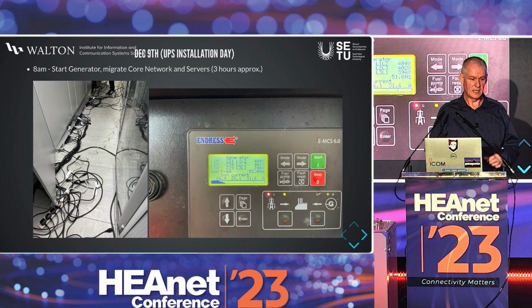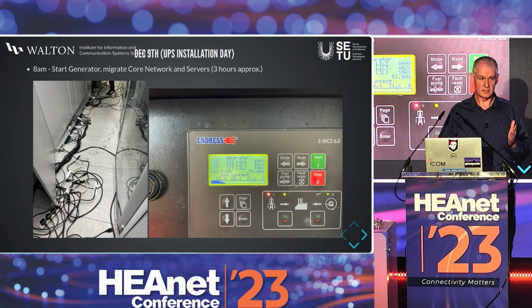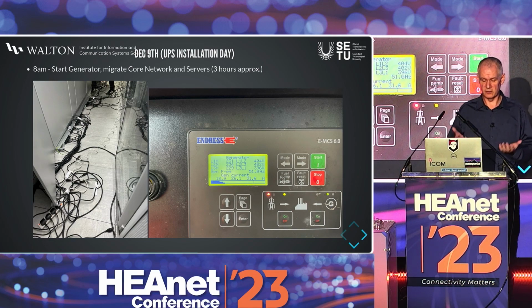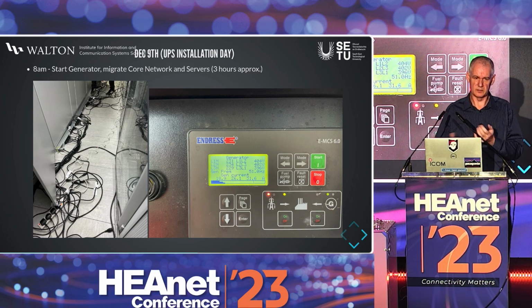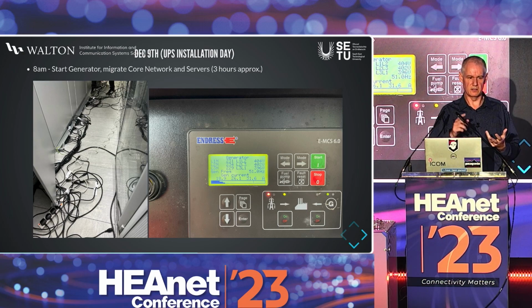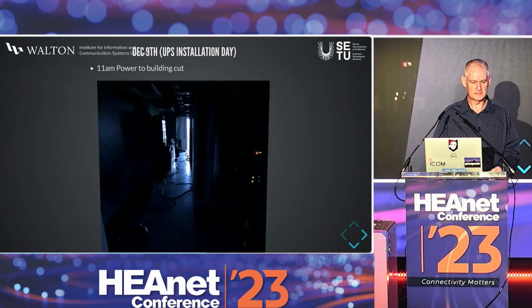So installation day - start the generator, start migrating stuff across. It took about 3 hours, longer than expected. Basically you migrate a server - everything is, or should be, dual fed, or on UPSs which take 2 feeds. Bring it across, check it, check the loading on the generator, and slowly, methodically move things across. We did the network room first, then the servers and the DC.